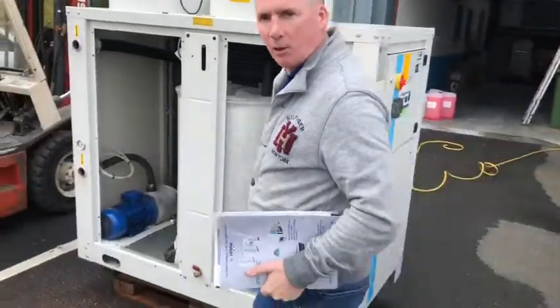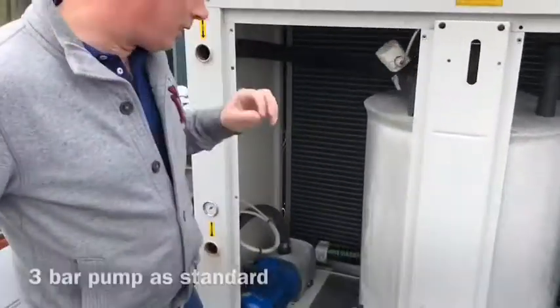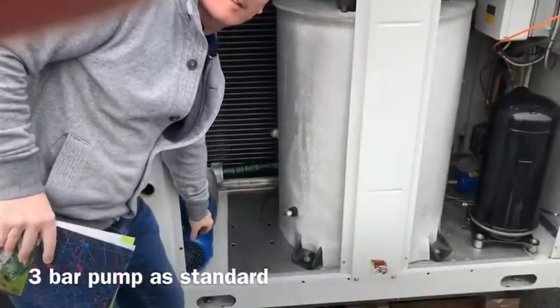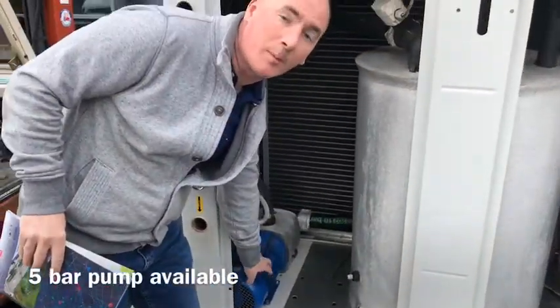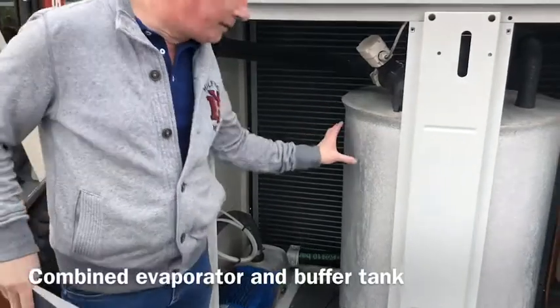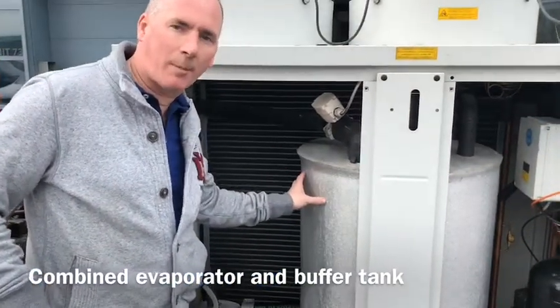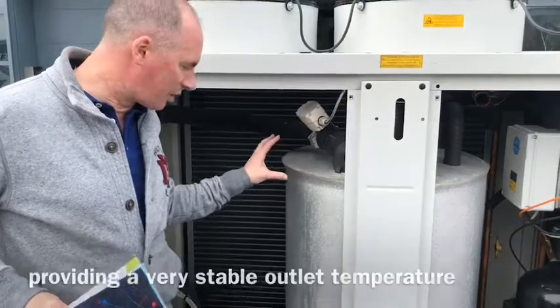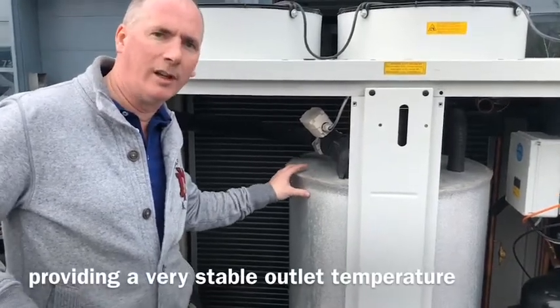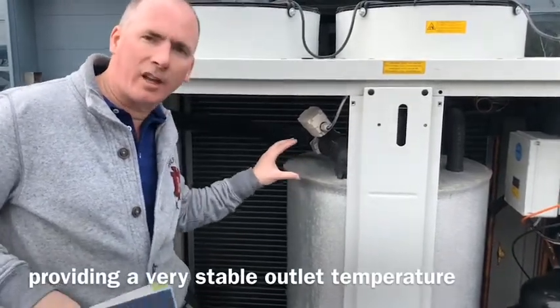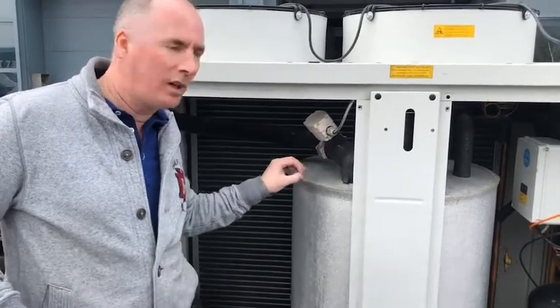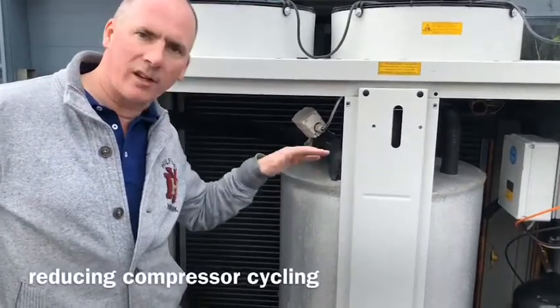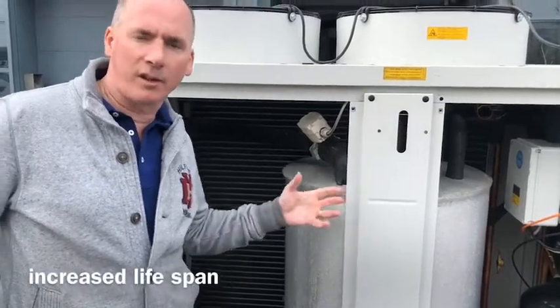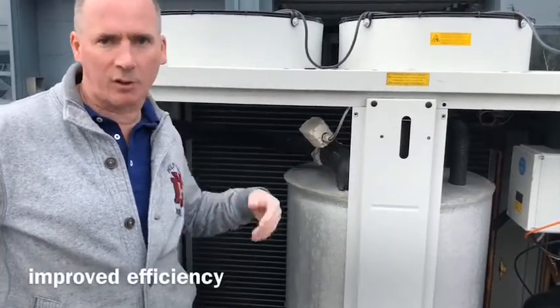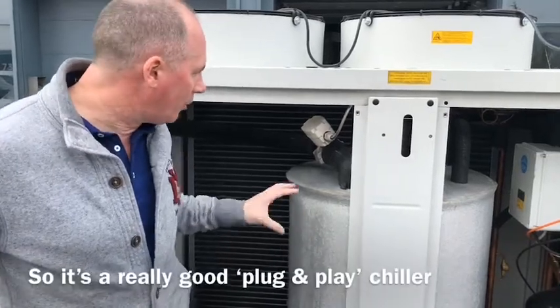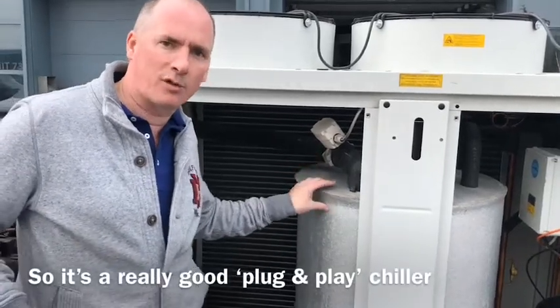So if you just come in close here, Martin. They typically have a much higher pressure pump as standard, typically about 3 bar, and we can get them up to about 5 bar. They have a built-in evaporator. It's a coaxial type evaporator built into the buffer tank, so it's a combined evaporator and buffer tank all in one. The logic of that is you get a very good stable outlet temperature. You get a lot less compressor cycling, start-stops, so the compressor lifespan lasts longer, and the efficiency is better because you don't have that start-stop. So it's a really good plug-and-play process cooling chiller.